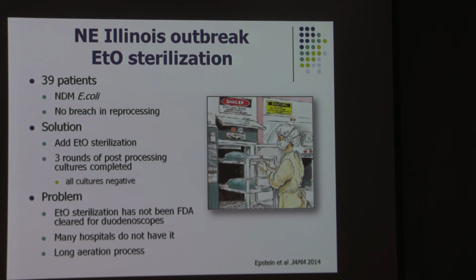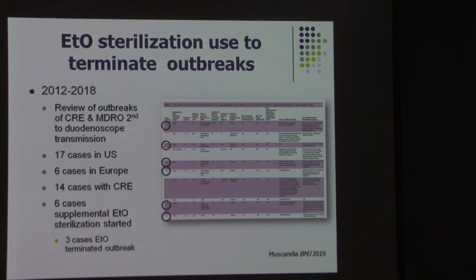However, as we all know, gas sterilization has not been FDA cleared for duodenoscope use. Many hospitals don't have it, and it requires a long aeration process. It seems like gas sterilization, though, has been the way to terminate outbreaks. This is a review of another review of outbreaks. As you can see, 6 of them used supplemental gas sterilization to terminate outbreaks.